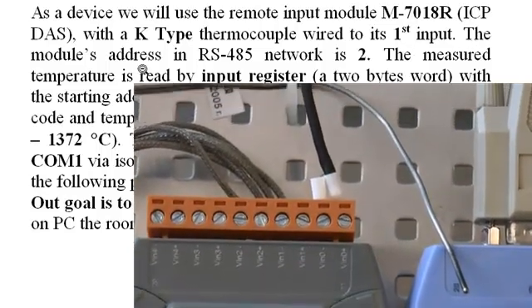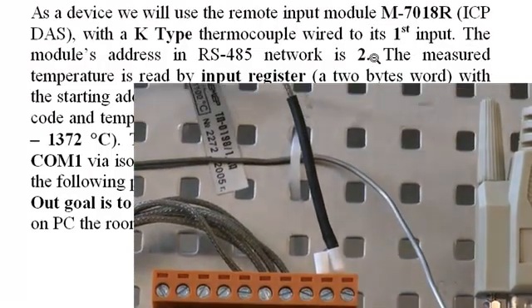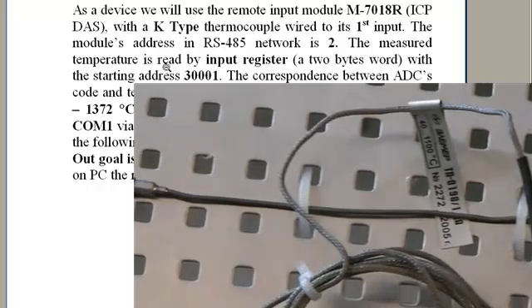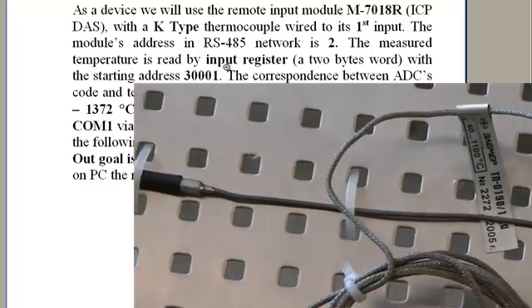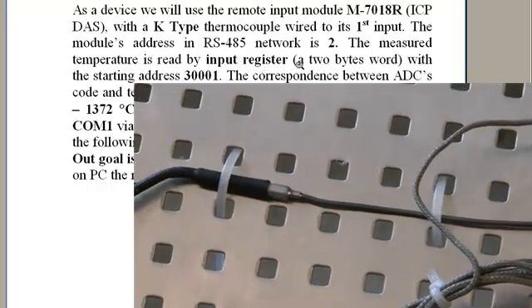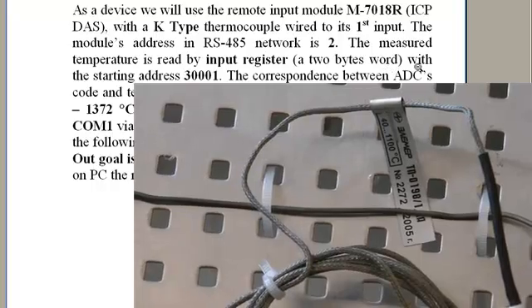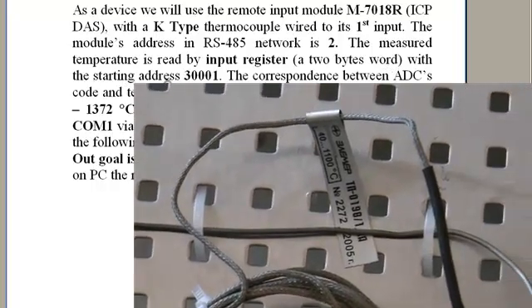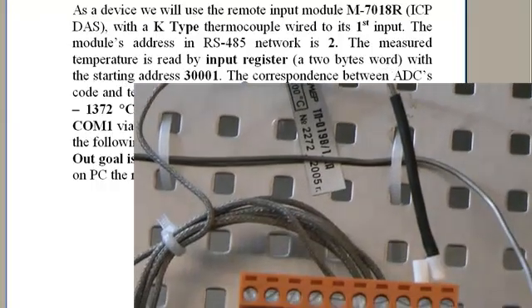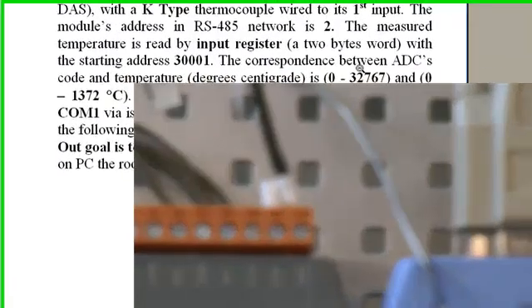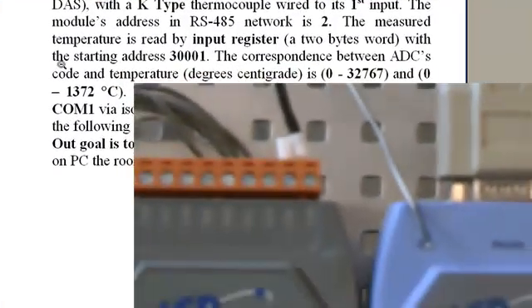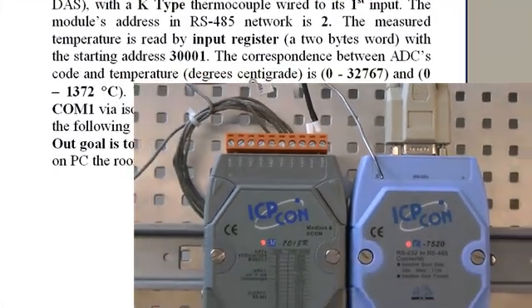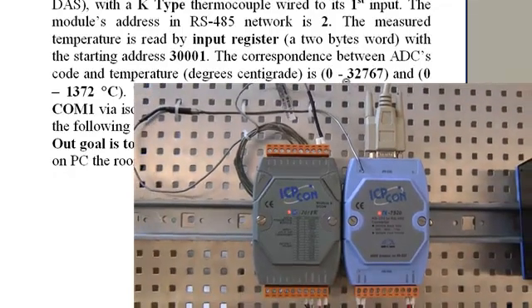The module address in network is 2. The measured temperature is read by input register in a 2-byte word with the starting address shown here. The correspondence between ADC code and temperature in degree centigrade is shown here.